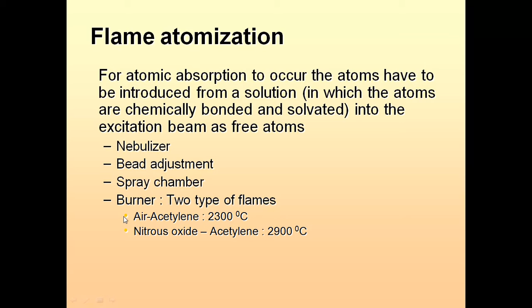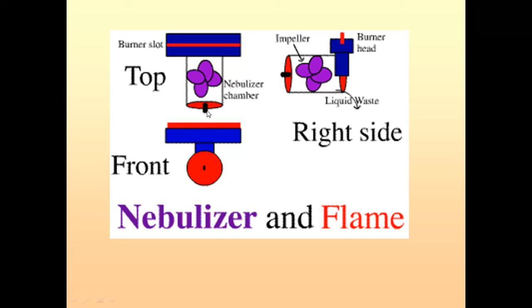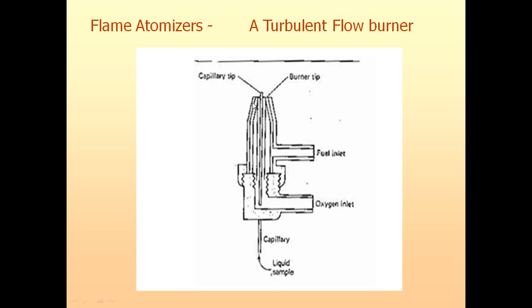And this is basically a nebulizer and the flame. So this is the front part and top view of the nebulizer. This is basically the port where the capillary is connected and the sample gets sucked into that towards the burner. So this is again a sketch of this nebulizer flame atomizer. This is the liquid sample where, through the capillary, the sample gets sucked, and from this side you are getting the flame, oxygen and the fuel, they get mixed and give you the flame. So this is basically the tip of the burner where the flame is there.